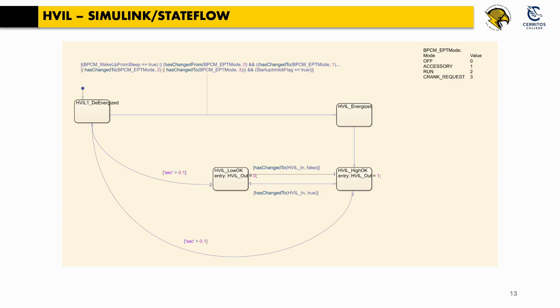This is when the input for the HVIL is at a high level. We basically need to check that nothing has failed at this point and that we switch quickly enough. If we don't switch quickly enough to the HVIL low state, then we end up back at the HVIL de-energized state, and then we begin checking again to see if we should energize HVIL.